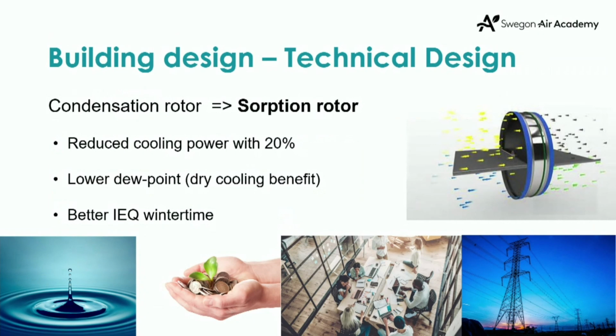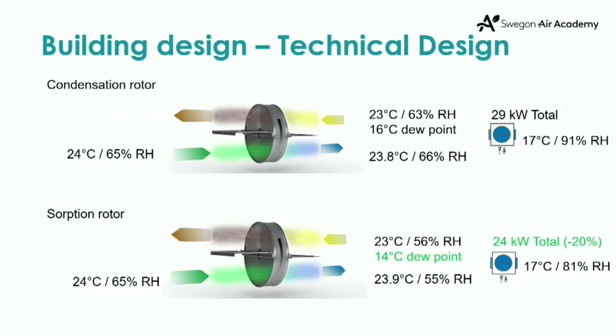But if we look at this from a technical point of view, what's actually happening here? If you look at the picture, with the same outdoor conditions, using a sorption rotor that returns most of the moisture, wintertime it takes it into the building, summertime it takes it directly out before it gets into the building, removing a lot of relative humidity from the outside air directly into the exhaust air. By doing that we can significantly reduce the cooling power needed in the building, and also reduce the relative humidity inside, lowering the risk of condensation indoors. So it's beneficial in many ways.